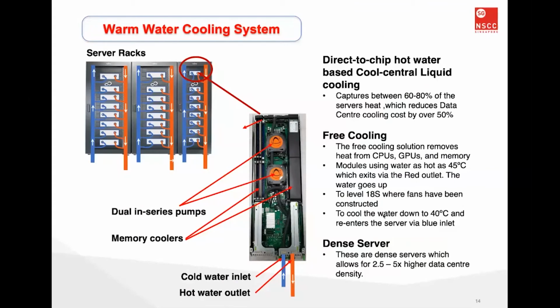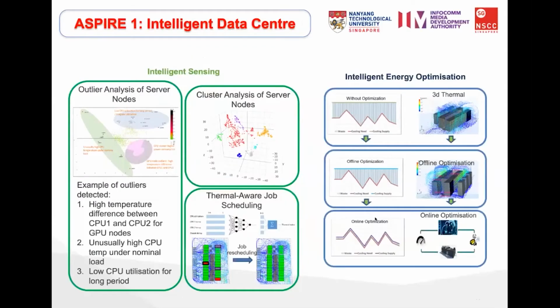The 45-degree outlet hot water goes out to an atmosphere running well below 40 degrees, maybe up to 35 or 36 on a really hot day. That temperature differential is sufficient for us to enjoy free air cooling. So our warm water cooling brings the heat from the chips straight to the atmosphere. Again, we are still throwing out heat. Can we further improve ourselves?